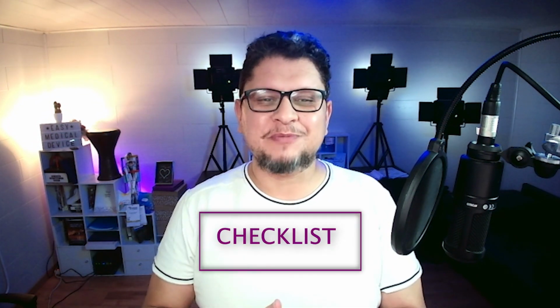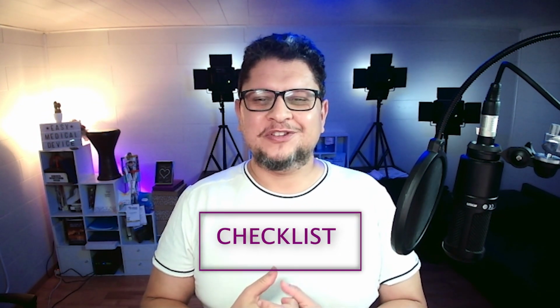Okay, so let's finish with the checklist. We'll see if you are responsible for post-marketing surveillance for your device or not. What questions should you ask yourself? Do we collect real performance data and not just wait for complaints? Do we have KPIs and thresholds for triggering some investigation? Do we have a defined process for revalidating updates? Do we document algorithm drifts, because for AI this can happen, and retraining decisions? Do we report findings transparently in the post-marketing surveillance and PSUR?